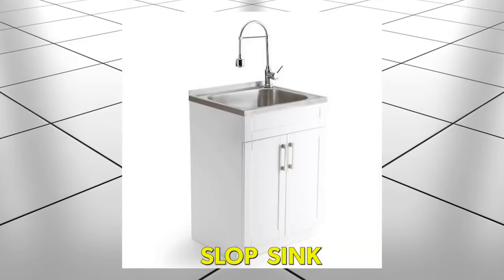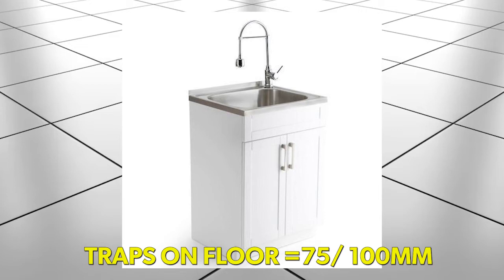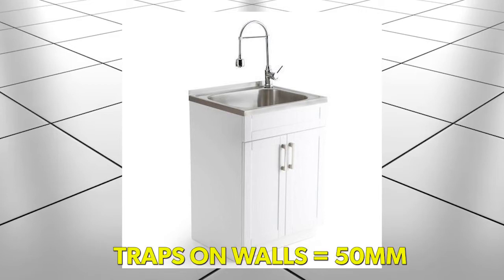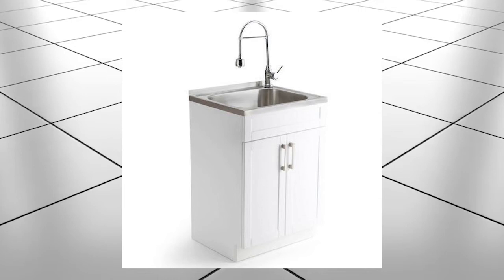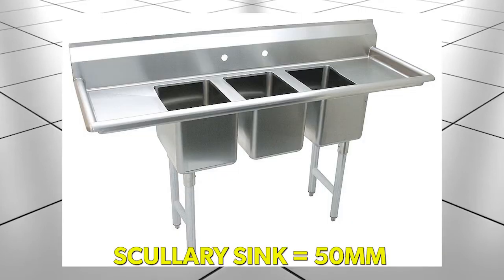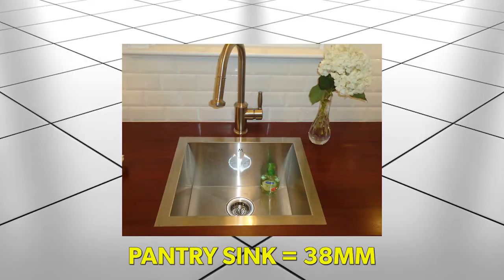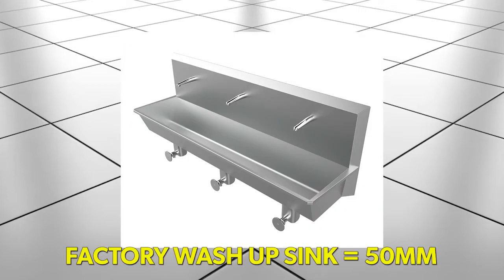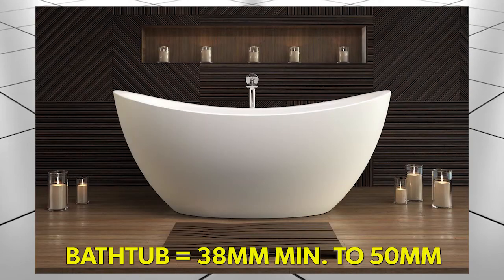2. Slop sink. Stop sink is tapped either on the floor or walls. Traps on the floor shall be 75 or 100mm and 50mm for traps installed on the wall with a cleanout plug. 3. Scullery sink, 50mm. 4. Pantry sink, 38mm. 5. Factory wash-up sink, 50mm. 6. Bathtub, 38mm minimum to 50mm. 7.